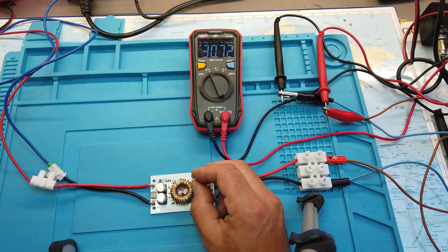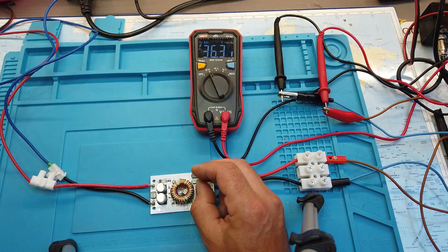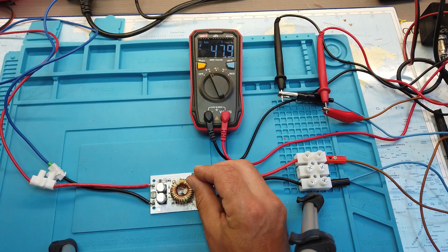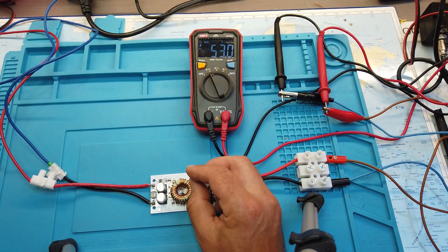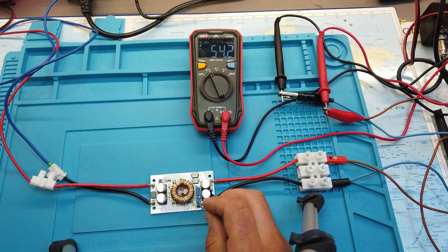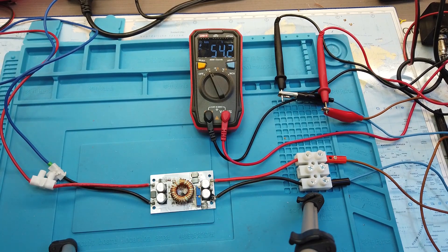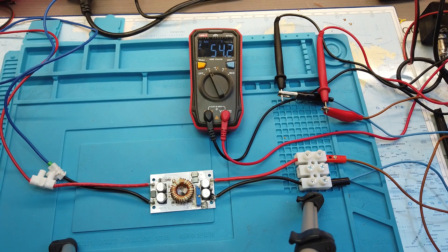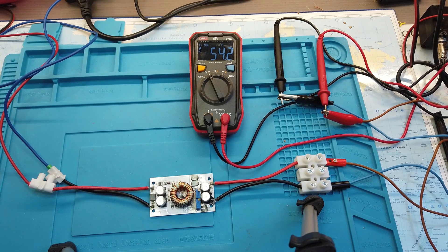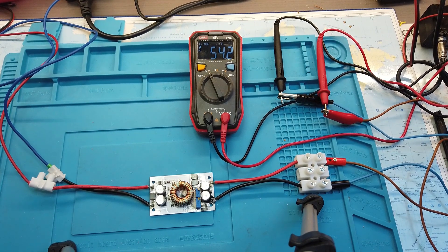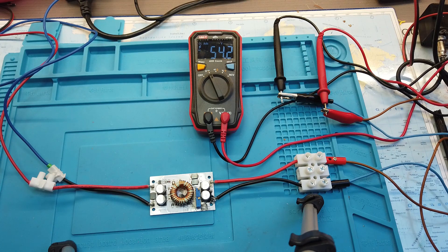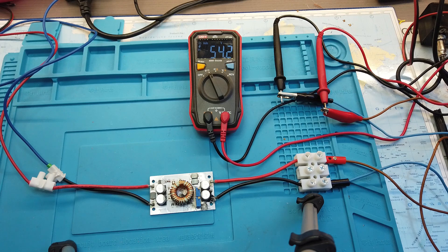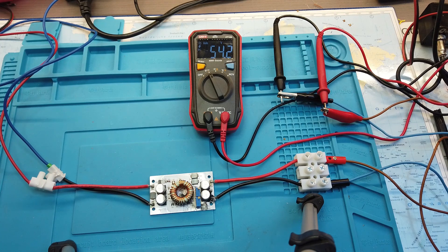Steady but slowly. 28, 34, and now 54. Then let it rest for like 30 seconds a minute. Let all the capacitors of your inverter pre-charge and this way your inverter is pre-charged. You won't have any sparks. You don't need to wear safety glasses or face covers or anything else. This is the magic solution.